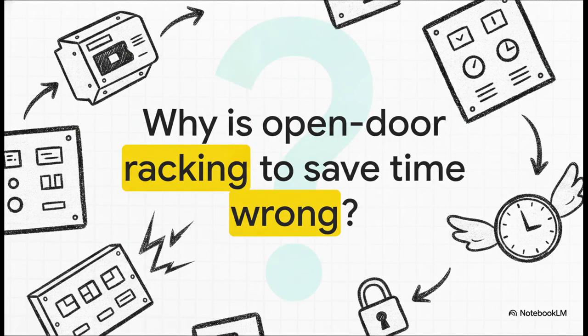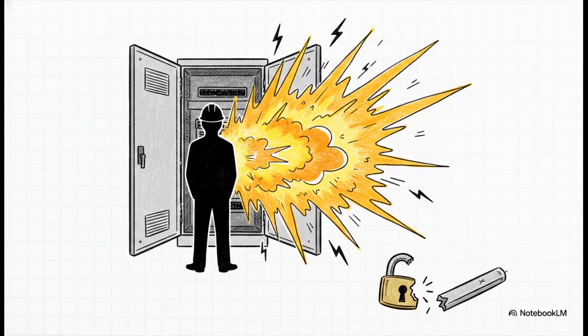Let's test this out with a real-world scenario. Let's say a technician wants to rack a breaker out with the compartment door wide open, just to save a few seconds during a really stressful turnaround or maintenance window. What's wrong with this picture? Take a second and think about the actual purpose of that interlock based on what we just covered. Well, the stark reality is that literally everything is wrong with it. You must never, ever override the door-closed racking interlock.